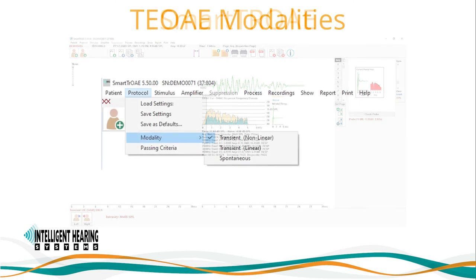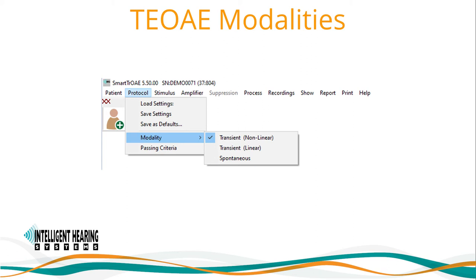Now let's move on to transient OAEs. Transient OAEs are generated by a non-linear system stimulated by transient stimuli, enhanced by an active process of the outer hair cells, and measured as a reflection. There are three testing modalities available. The first is non-linear, used for high-intensity recordings such as typical clinical TE-OAE measurements at 80 to 95 dB SPL. The second is linear, used for low-intensity testing such as suppression testing at 65 dB SPL. The third is spontaneous, which does not use a stimulus — it records any response present with or without a synchronization click.